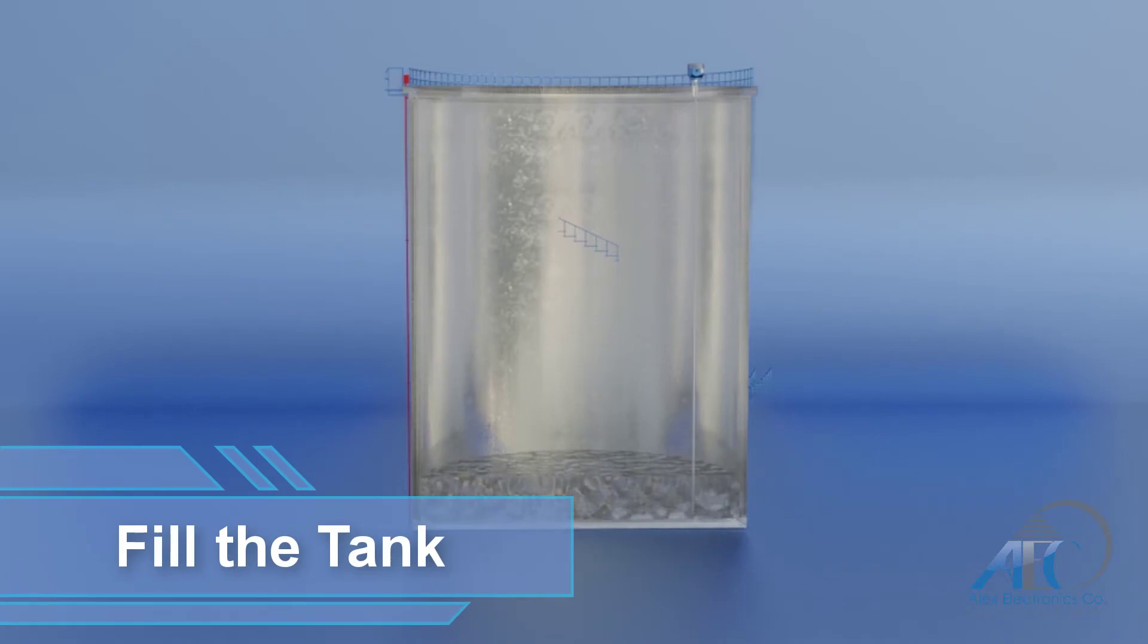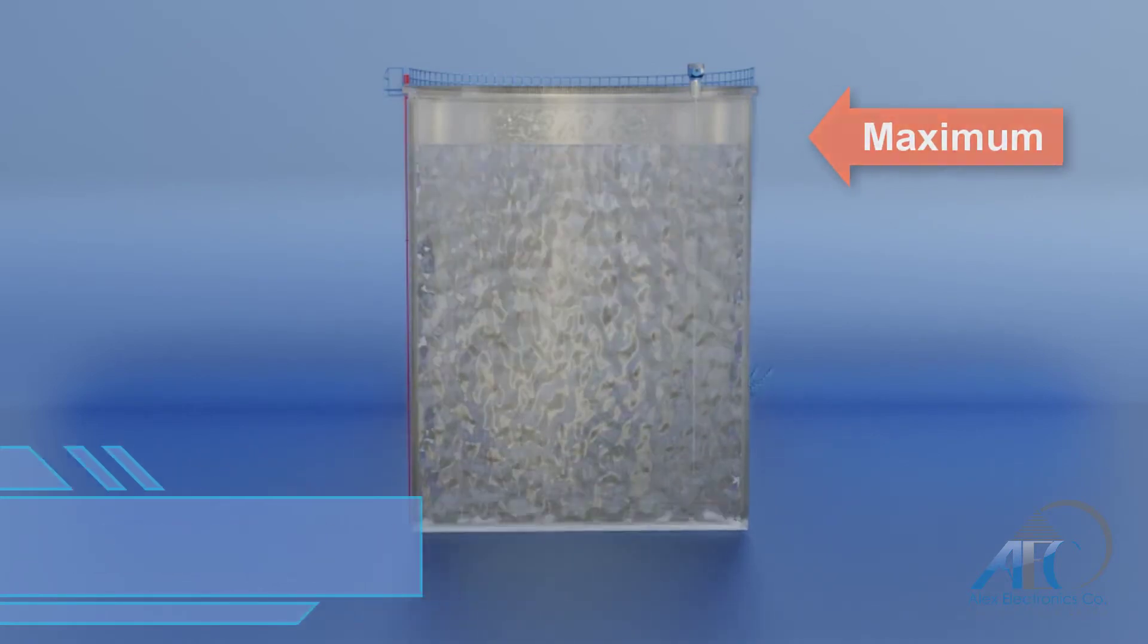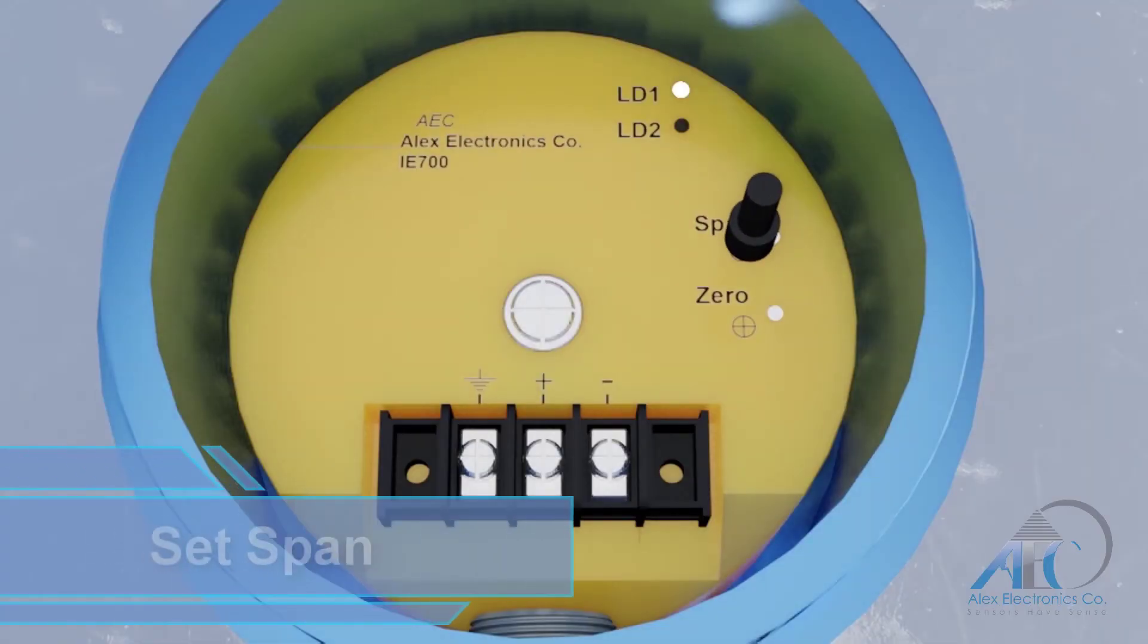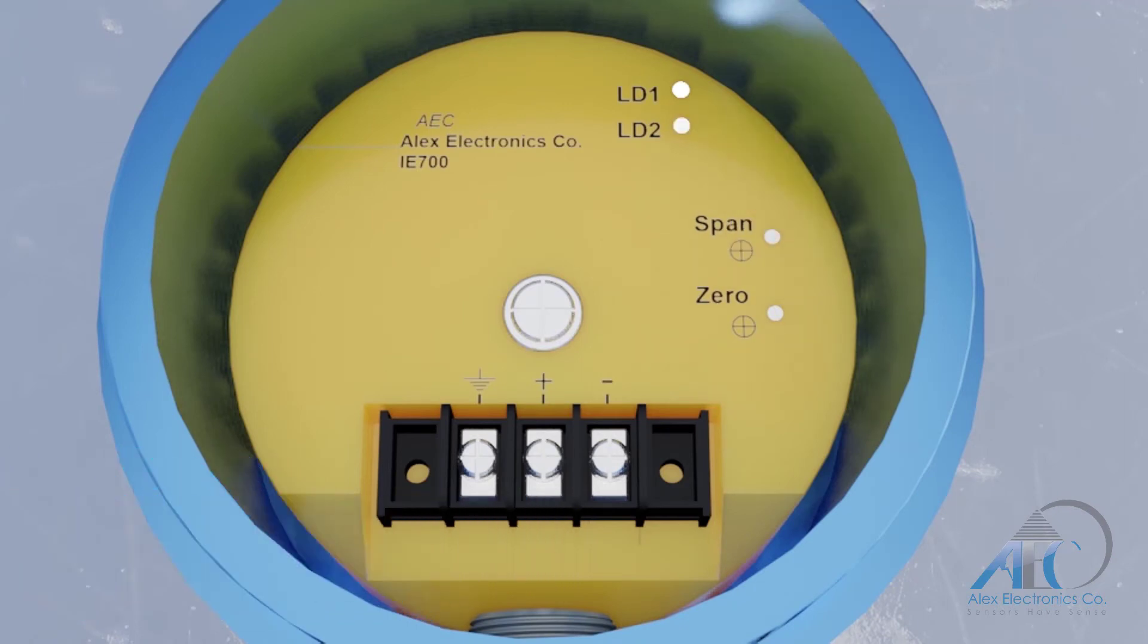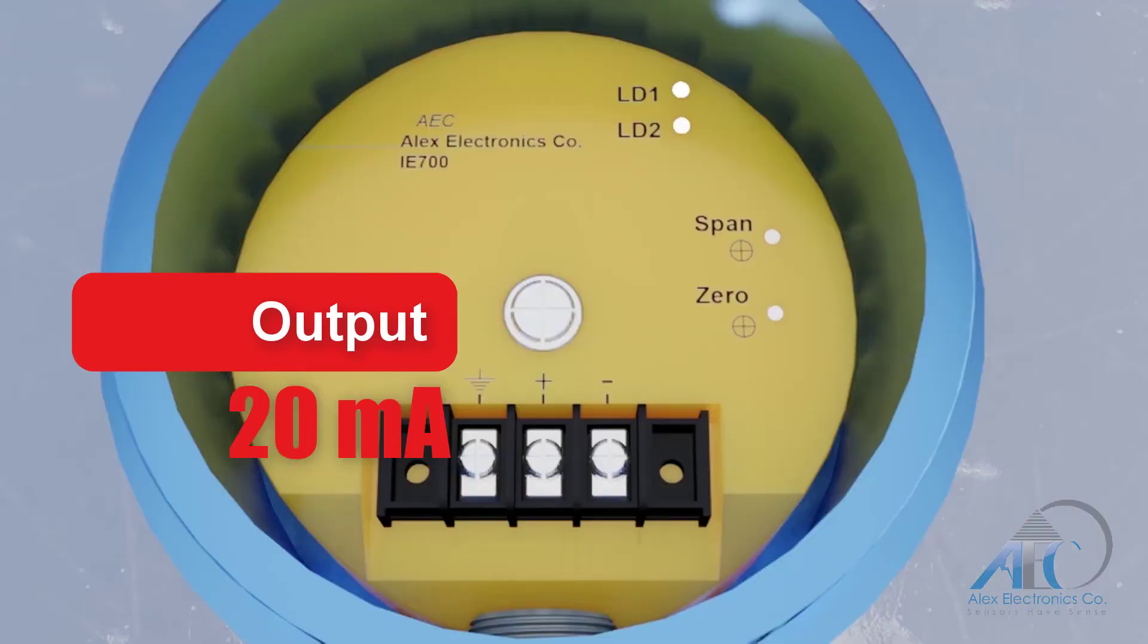To set the span, you need first to fill the tank to its maximum level. Then use the magnetic pen with the span programming circle in the same way as shown previously. At this point the output signal is 20 milliampere.